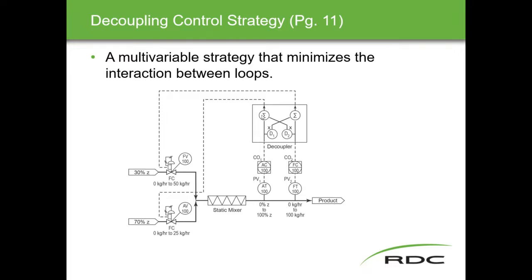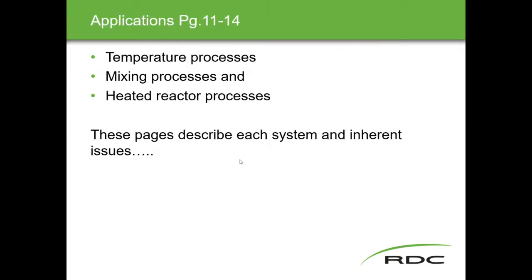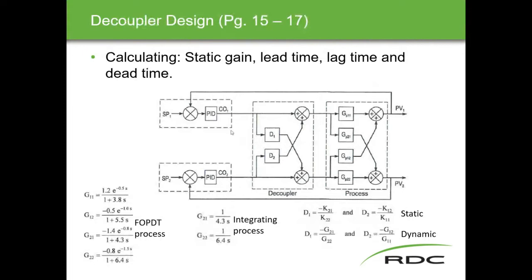The RGA leads us into the decoupling control strategy. Knowing the interaction between the two loops — one affects the other by a factor of three, the other by 1.49 — we can calculate values to put in the decoupler to minimize the effect of one change on the other loop. Common applications for decoupling include temperature processes, mixing processes, and reactive processes. You can read about them on pages 11 to 14 of the ILM.